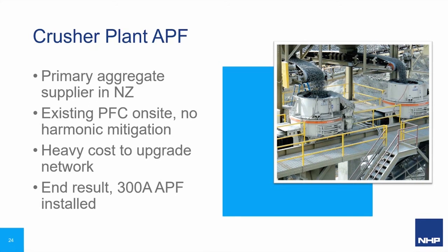But when the new variable speed drive system, or VSD system, was supplied by NHP, the new system allows one motor to act as a speed master, and the second motor operates as a torque slave, thereby equally sharing the rock crusher load. However, the consequence of almost fully loading the 750 kVA transformer with VSD load meant that the harmonic voltage distortion levels on the 415 volt bus were in the order of 11 to 12%, which is far in excess of the usually accepted 5% maximum.